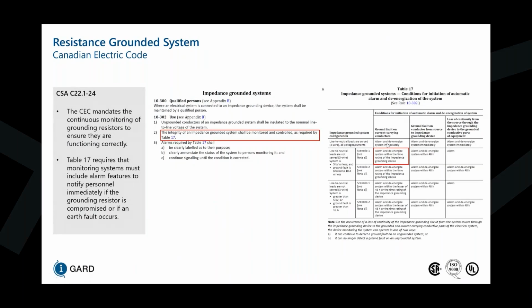At I-Gard, we recommend not to distribute the neutral in a resistance grounded system because it's considered dangerous, and it's also banned by NEC 250.36. The reason is that when a ground fault does occur, the neutral voltage elevates, and it can definitely impact those single-phase loads when a ground fault is present.